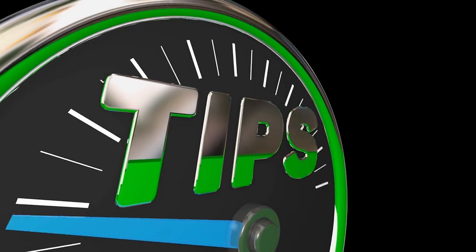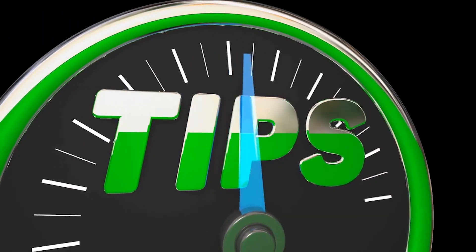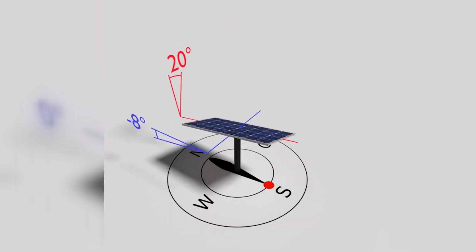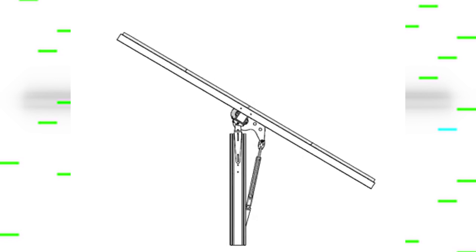There are key factors to consider when designing a PV project to mitigate the dust problem. The first tip is to choose the PV module tilt angle optimally. An increase in the tilt angle impacts the stability of dust particles. For a perfect spherical configuration, up to a critical angle of 23.4 degrees stability is possible, and over that angle an avalanche procedure takes place.